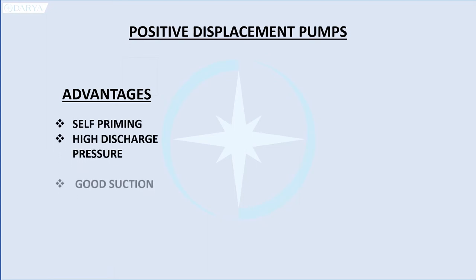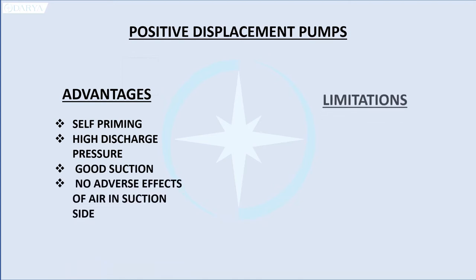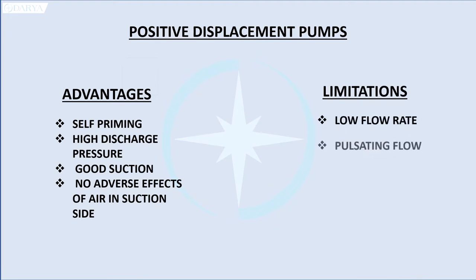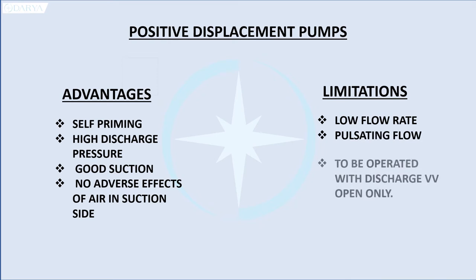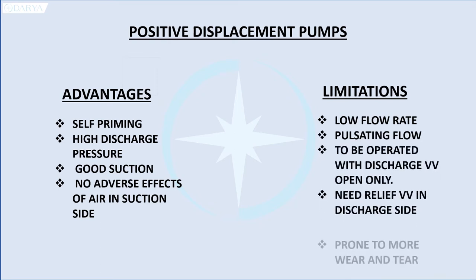There are no adverse effects of air in suction side. Their limitations are they have low flow rate, they are pulsating flow, they are to be operated with discharge valves open only, they need relief valve in discharge side, and they are more prone to wear and tear.